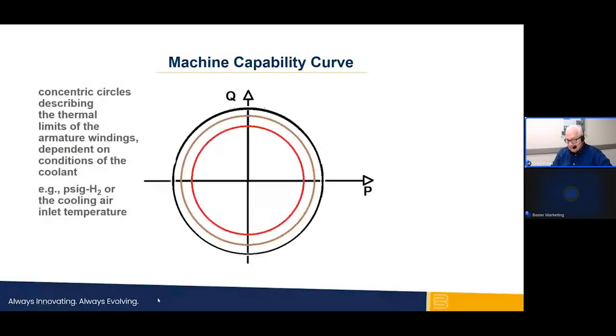Since the thermal limits of the machine depend on conditions of the cooling system, the radius of the limit circle will vary accordingly. These cooling conditions are not under control of the excitation control equipment, but they can be monitored for use in recalibrating limits that are based on thermal concerns. You can see the concentric circles in this diagram to derate for higher temperatures.